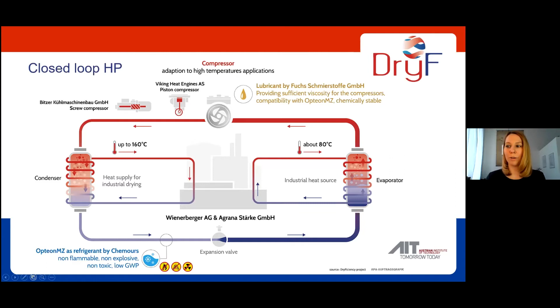Due to the size of the heat pump, and also to be able to measure exactly the heat supply temperatures, we have integrated the heat pumps with an intermediate water cycle. The heat pump provides hot water, which is used to heat the air, and within that water cycle we were already able to measure the 160 degrees C heat supply temperature that we were aiming at in this project.